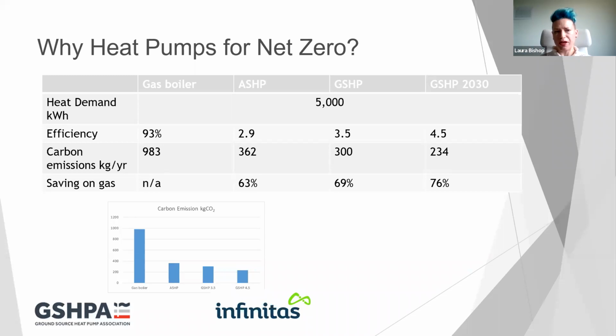If you were to put in an air source heat pump, I've used a very conservative coefficient of performance of 2.9, but we have to be aware that with air source, when you need the most heat is when they are at their least efficient, because the outside air temperature is low, and you've also got to take into account defrost cycles. So your overall efficiency in the year won't be as high as with ground source. But we do know that the majority of heat pumps going into housing over the next few years will be air source. So with an efficiency of 2.9, carbon emissions using 2021 government figures for electricity come to 362 kilograms per year, a saving of 63% on gas. So even if everybody put air source heat pumps in, ignoring the impact on the national grid, you'd straight away get a saving of 63% on baseline.